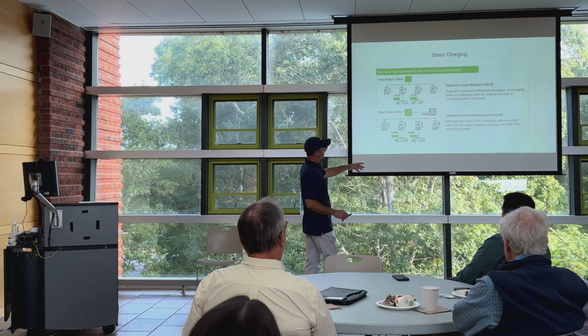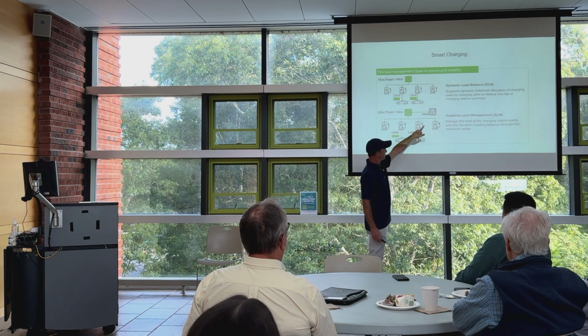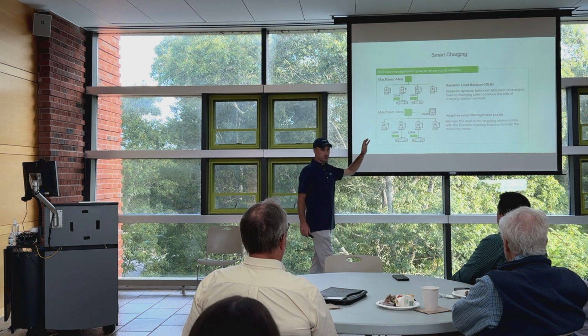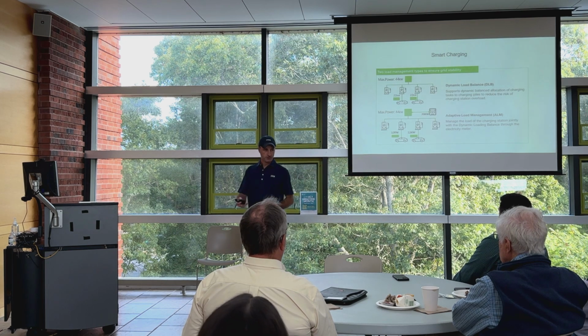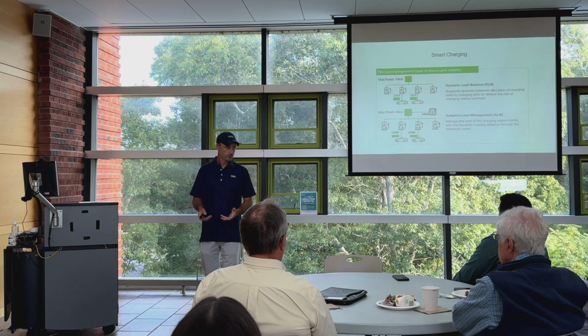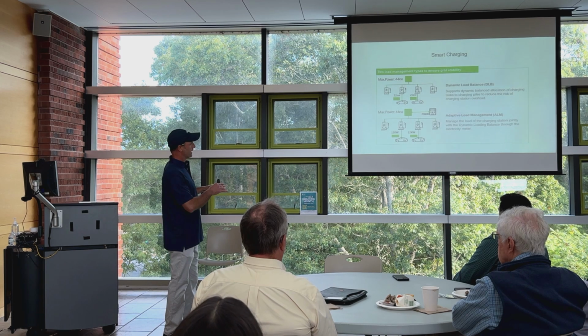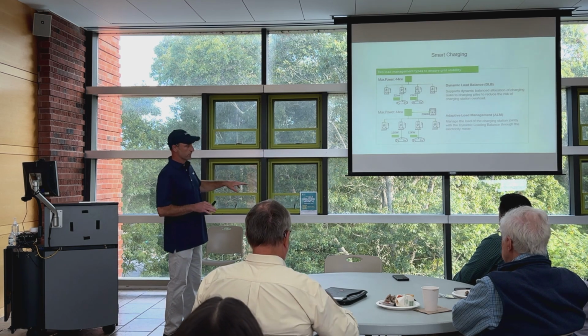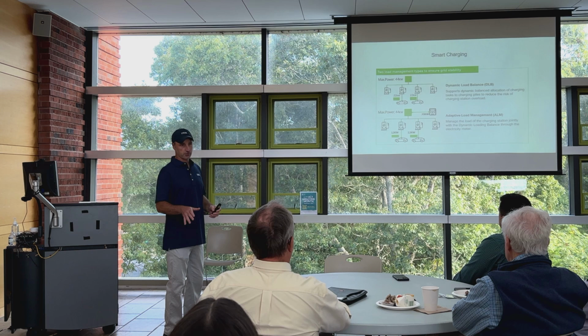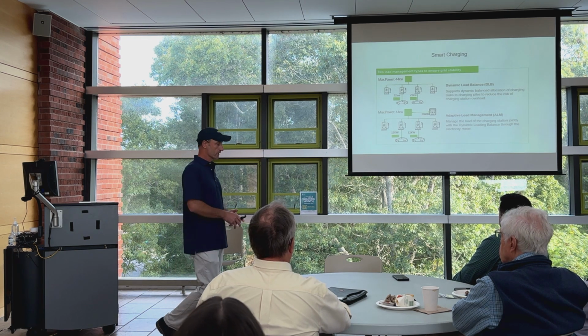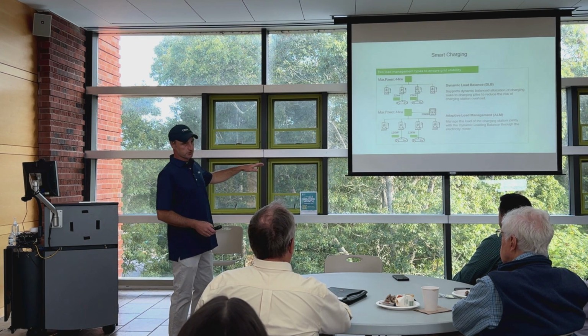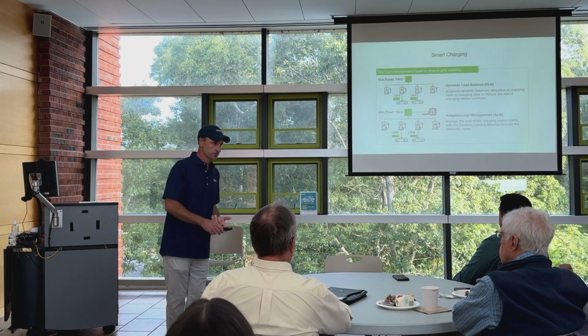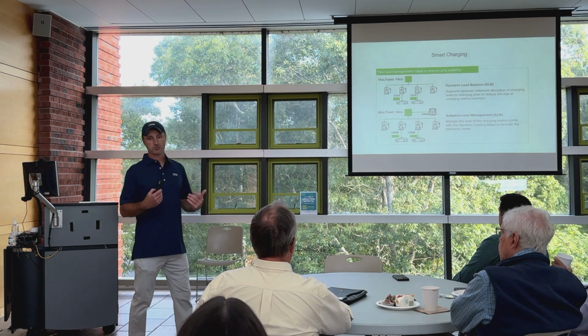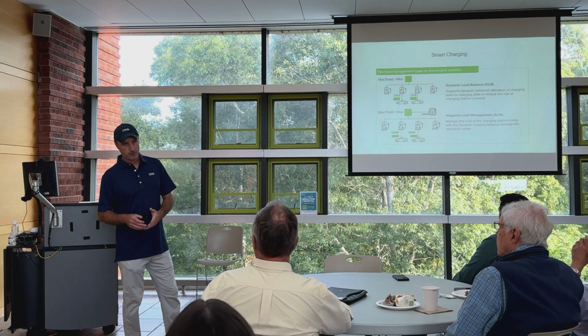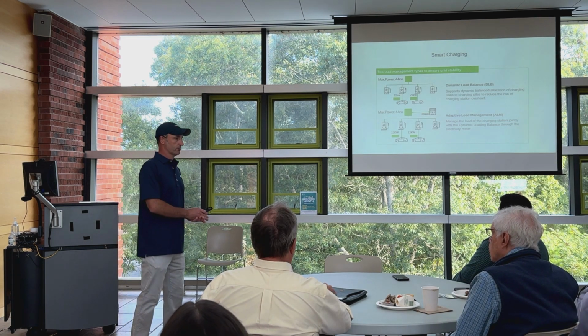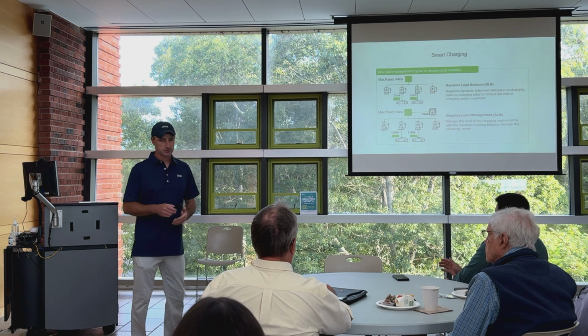Then there's adaptive load, which measures the amount the building itself is using. In the evening, with the lights on, there's not as much energy on site to go around, so they share that, and the smart charger's software knows how much energy can be delivered safely without blowing the breaker. We're not using adaptive load as much right now because the systems we're putting in are independent - we're not drawing off house power. We could, but we want our systems separately metered because the energy cost is discounted.